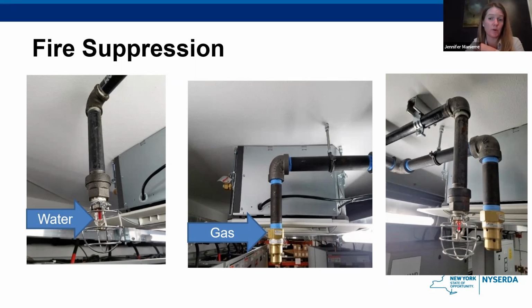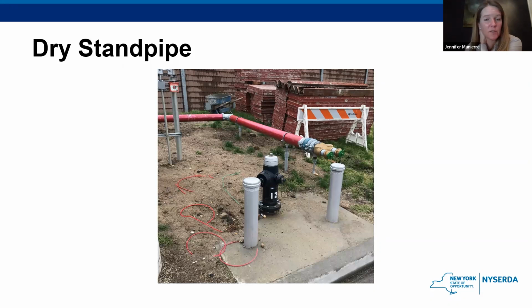And in some cases, you might want both, like the picture on the right. Maybe you have a gas suppression system to snuff out any flames, maybe in a different piece of the equipment in the room, and secondary, the water, if the primary does not do the trick. Okay, for some outdoor systems, it might make sense to use a dry standpipe. It can get pretty cold here in New York, and we wouldn't want the water in the pipes to be frozen should an emergency occur. So sometimes you will see a dry standpipe that can be filled by the fire department upon responding to an incident.